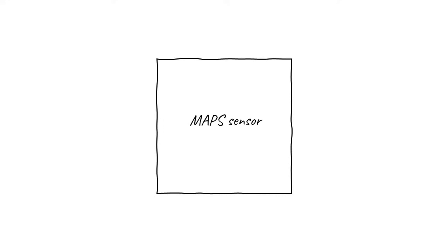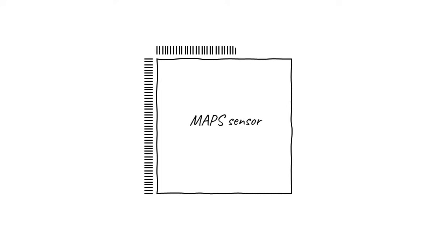We start with a CMOS monolithic active pixel sensor, commonly called a MAPS sensor, which is radiation-hardened and can detect direct bombardment by electrons in a TEM. The sensor is attached to a circuit board that reads and resets its pixels. When an electron hits the sensor, it deposits a variable amount of energy in one or more pixels, resulting in voltage accumulating within the pixels.